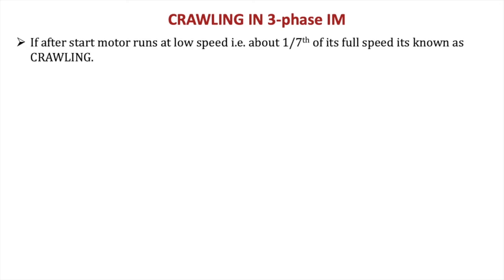Now we'll discuss two things, that is crawling and cogging in the given motor. First, let's try to understand what crawling is. Sometimes you'll observe that the motor has not picked up speed but is running at a very slow speed. That is known as crawling, and this very low speed is normally 1/7 of its full speed. So we'll try to understand why this is 1/7 of its full speed.